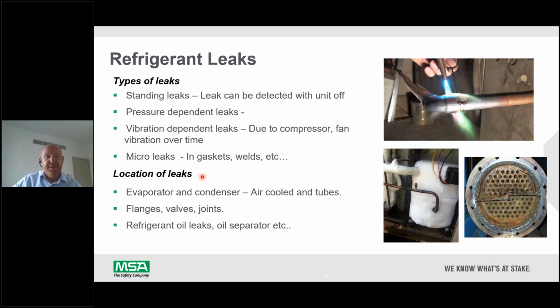The majority of leaks occur in the evaporator or the condenser. This is where you have the largest surface area of material, copper usually, in order to transfer heat. So it's the highest risk area which has gas. It's also where the refrigerant changes phase from liquid to gas or gas to liquid. So there's a lot going on in the evaporator and condenser.